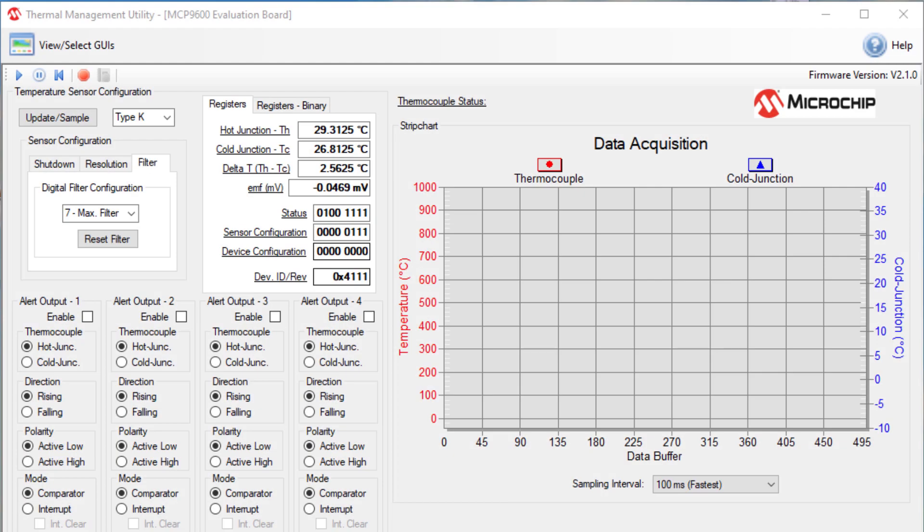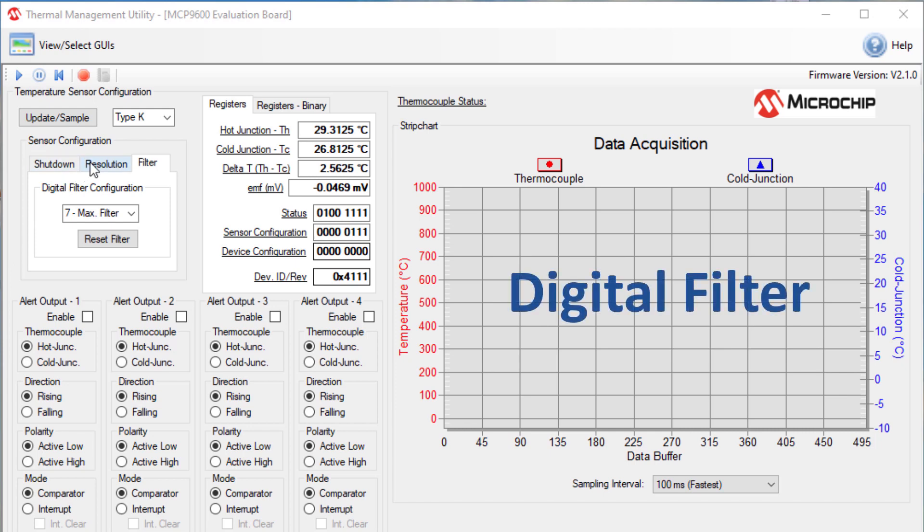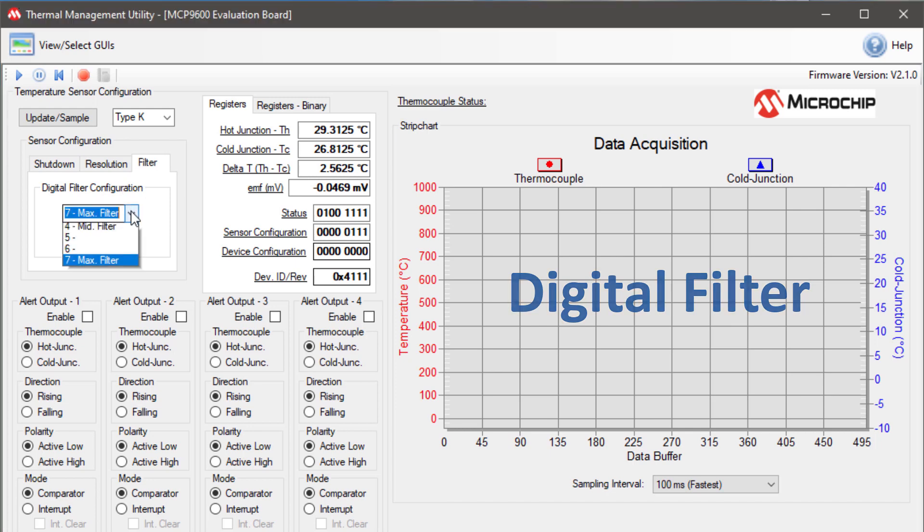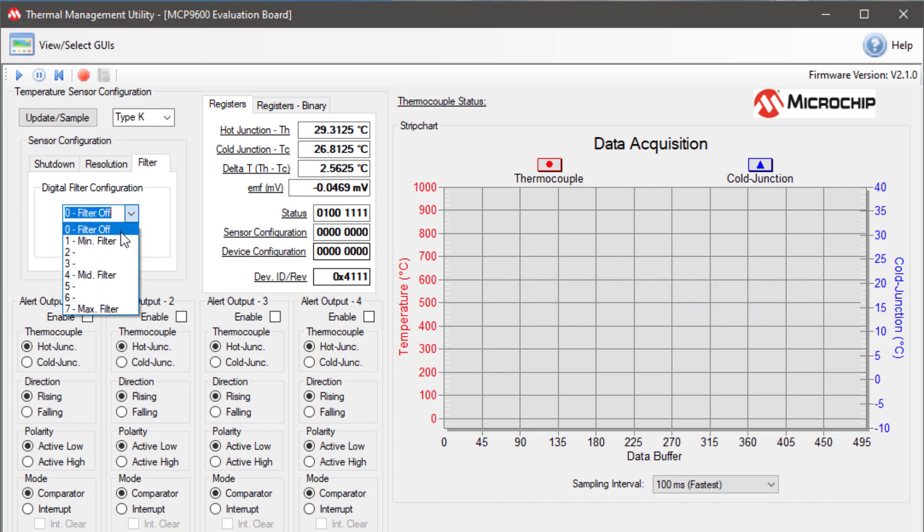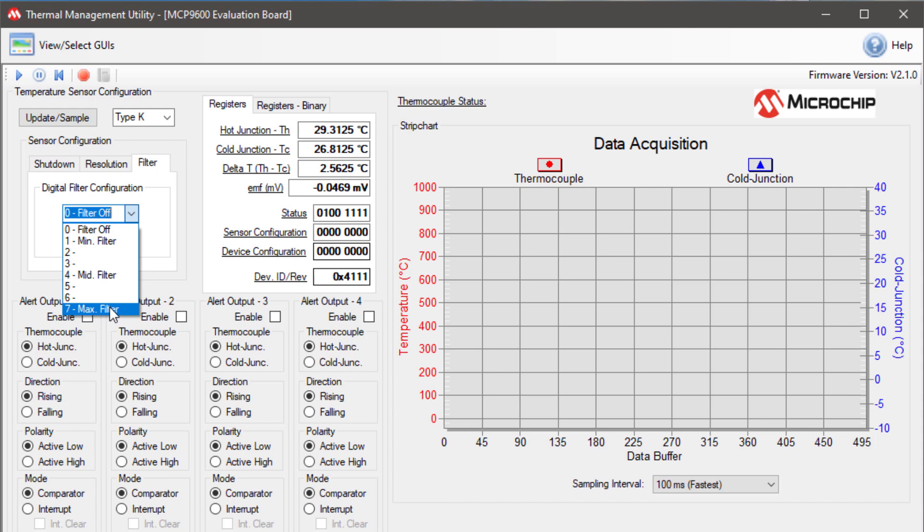For this video, I'm just going to do a graphical demonstration of how the digital filter feature operates. As you can see, under the digital filter configuration, on the drop-down menu, it has all the different selectable filter settings. It ranges from 0 to 7. 0 means that the filter is off. 1 is minimum filtering, 4 is mid-filter, and 7 is maximum filtering.